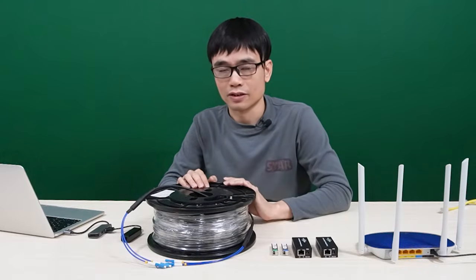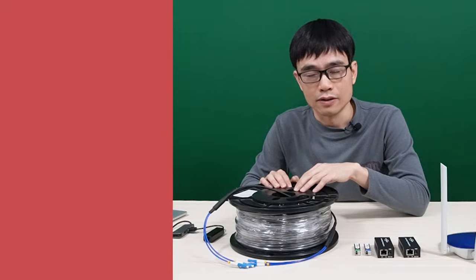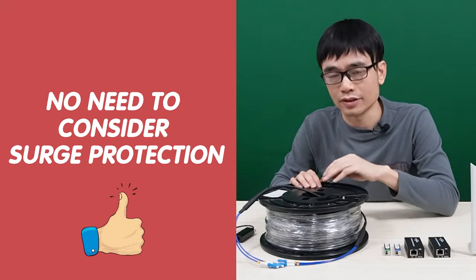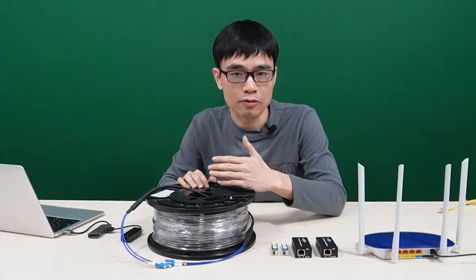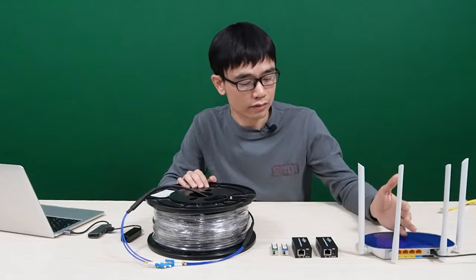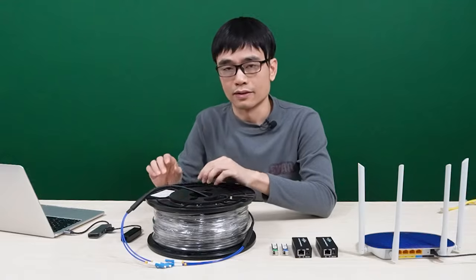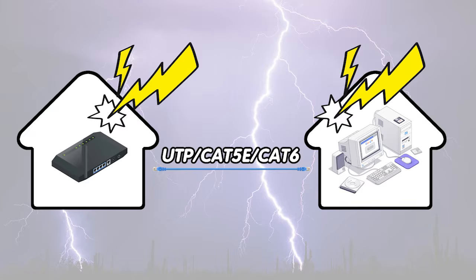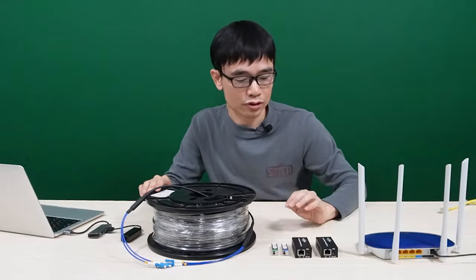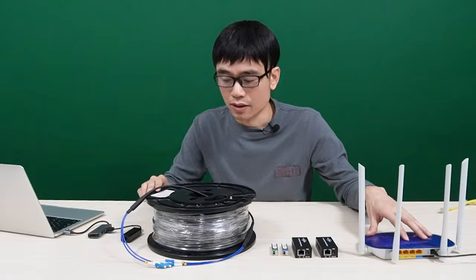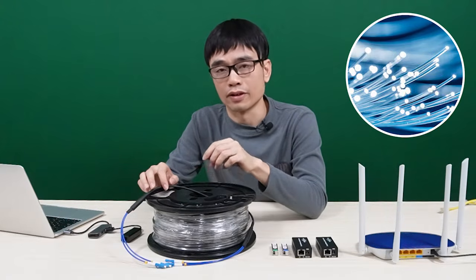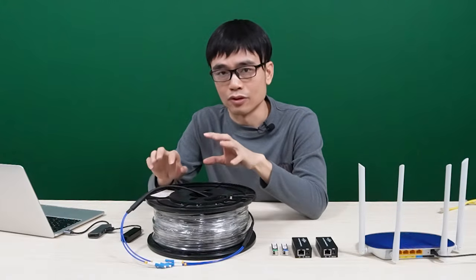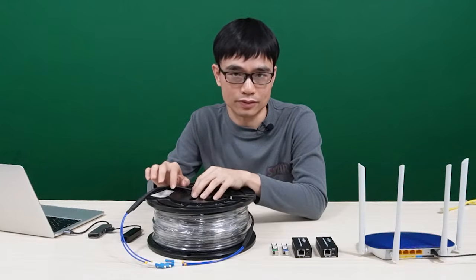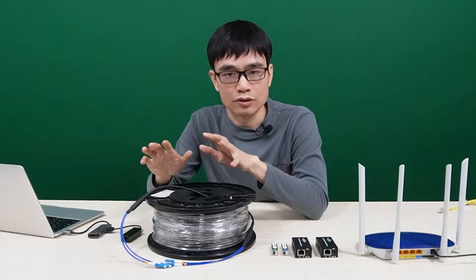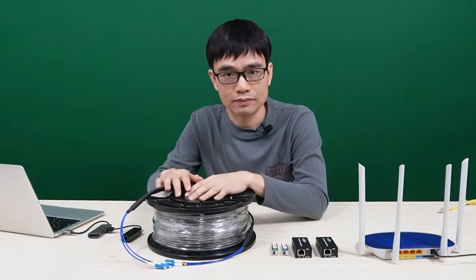There's one more feature you get from the fiber optic cable: you don't need to consider surge protection. When we pull the UTP cable, Cat5e or Cat6, from the router or modem to a remote location, the cable could attract a surge, and the surge can travel to both ends. It may eventually damage your edge device or the router. The fiber optic cable is made of glass, so there's no way the glass could attract a surge. We don't need to have surge protection, at least for the cable side.